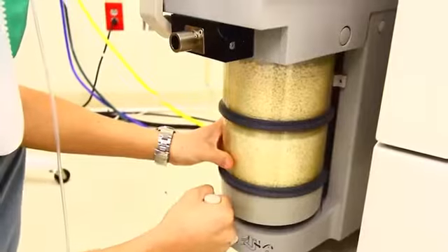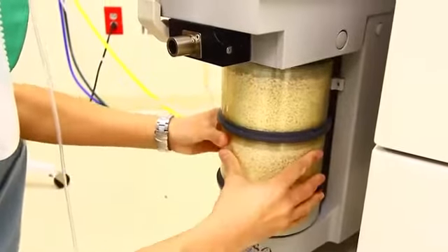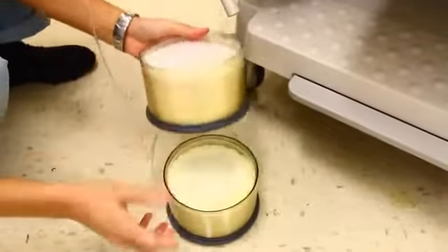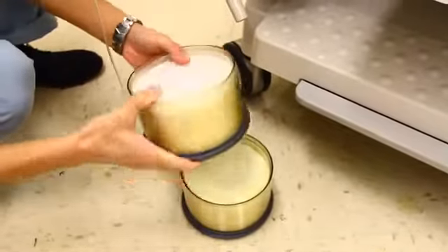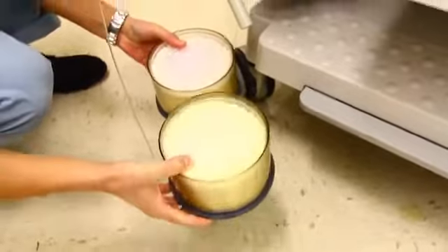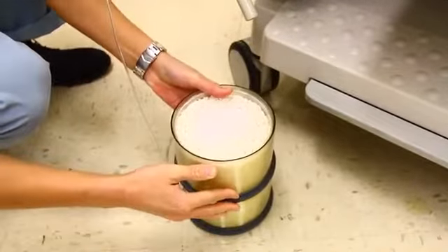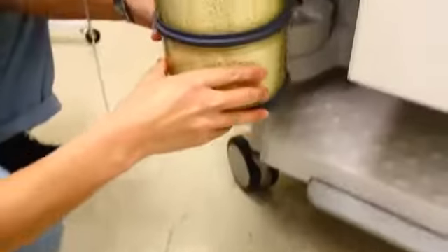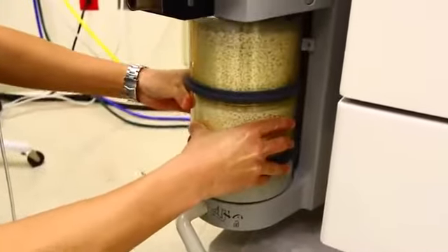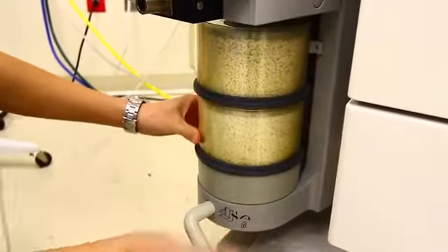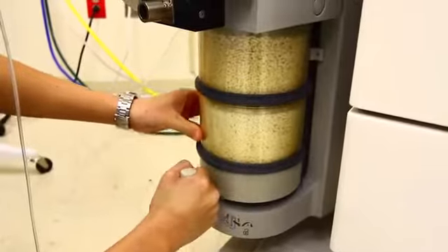To remove the CO2 absorbent canister, you must first pull the handle out and turn it clockwise until it stops. Take each canister and shake it to prevent channeling. Place the canisters on top of each other, place them back into the holder, and turn the handle counterclockwise until it locks.